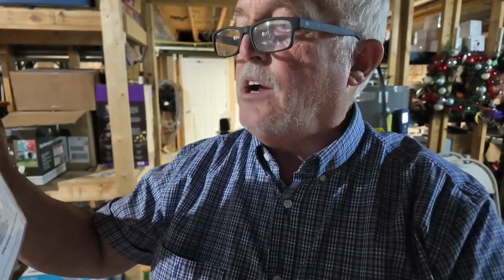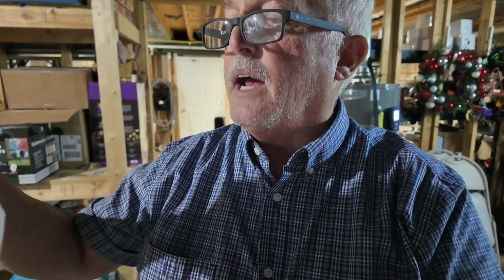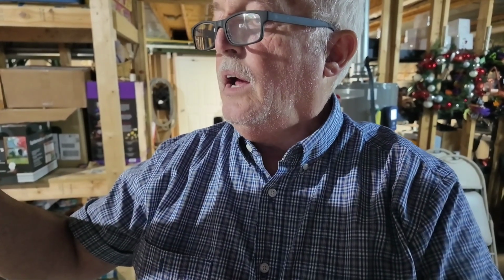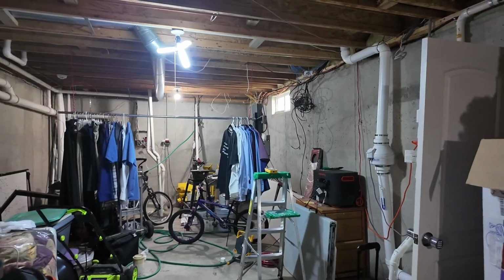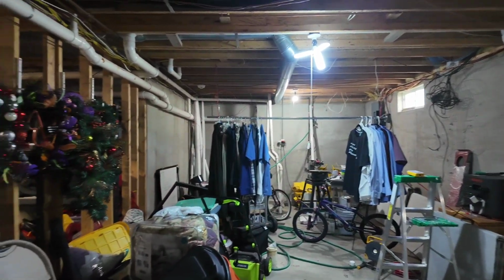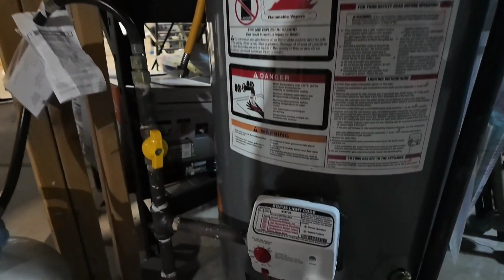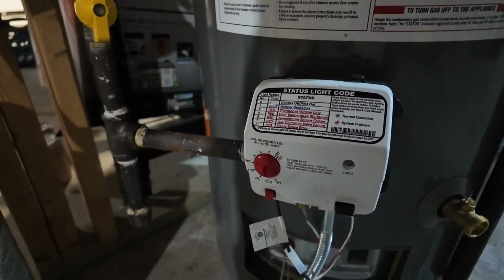And if we look at our guide, it tells us what our action levels are for CO. And in this particular case, it is a water heater. And a water heater is 200 parts per million, CO air free. And we were below 200 parts per million. Now we're going to put everything back in their standby mode. In this particular case, the water heater goes back to pilot or off position.